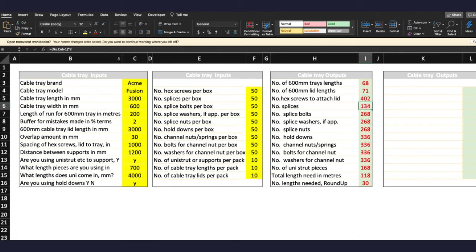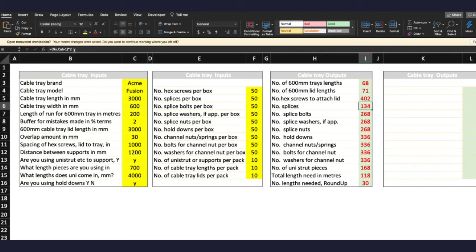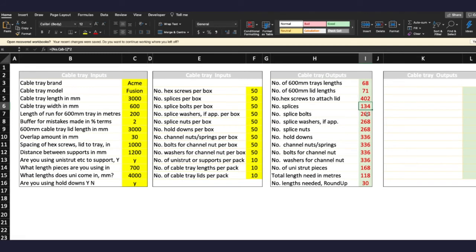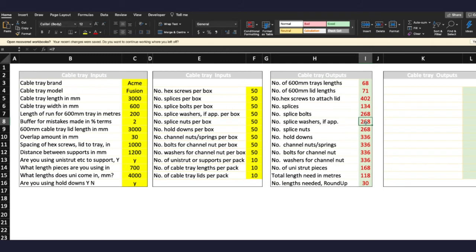Splicers, so the splices, they relate to the number of cable tray lengths minus one. And like panel framing joiners, it's the same thing. Then you multiply that by two because you have two splices per join. And number of splice bolts, okay well you can see here that I've just referenced the amount of splices and multiply by two because you need two bolts. And now washers, if applicable, that references the number of splice bolts and number of splice nuts.